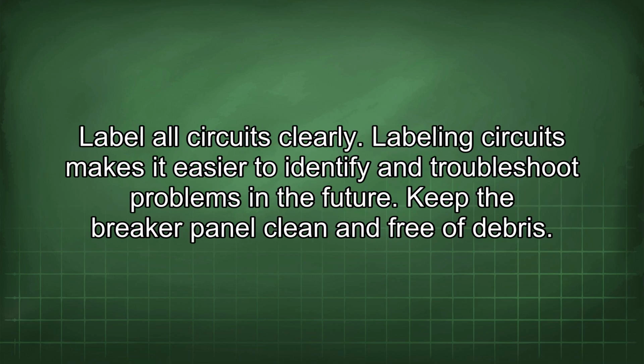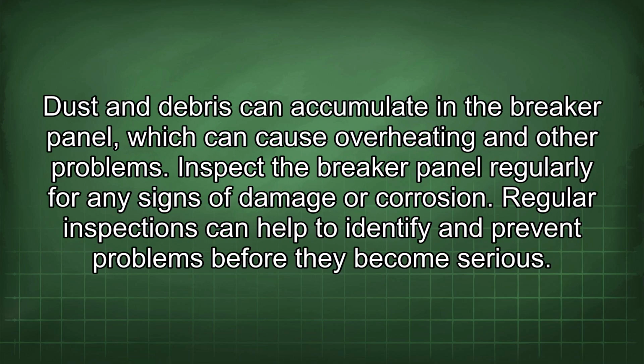Label all circuits clearly. Labeling circuits makes it easier to identify and troubleshoot problems in the future. Keep the breaker panel clean and free of debris. Dust and debris can accumulate in the breaker panel, which can cause overheating and other problems. Inspect the breaker panel regularly for any signs of damage or corrosion. Regular inspections can help to identify and prevent problems before they become serious.